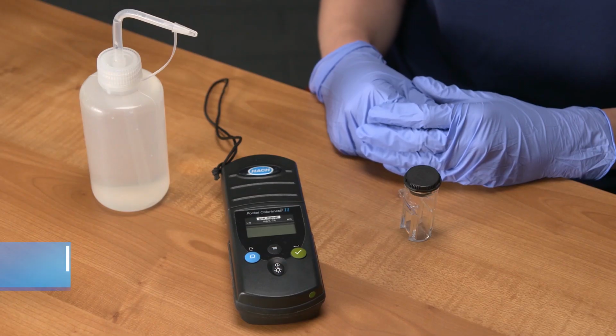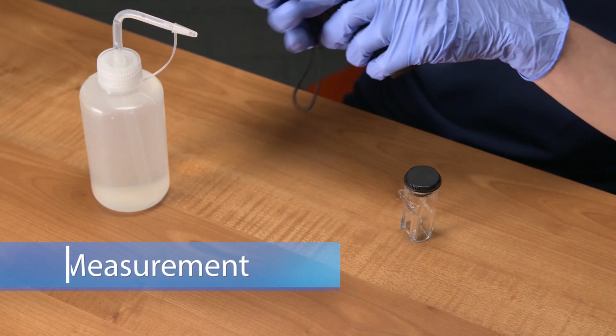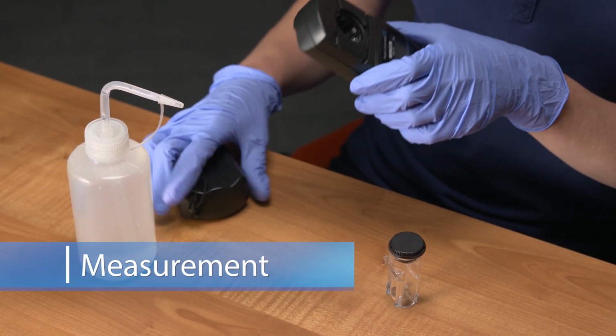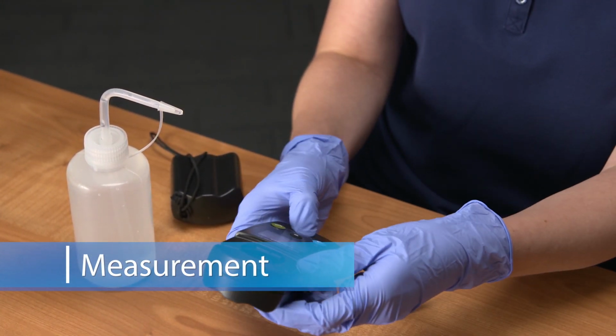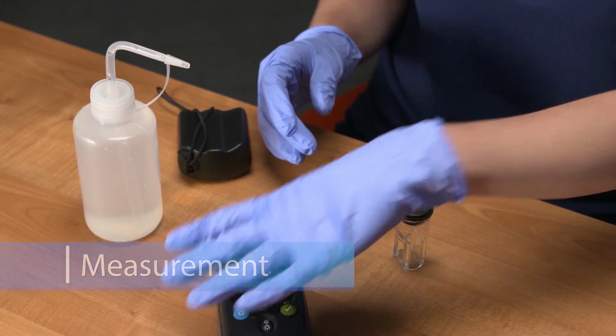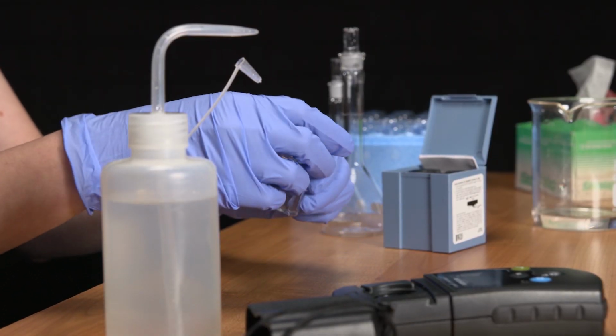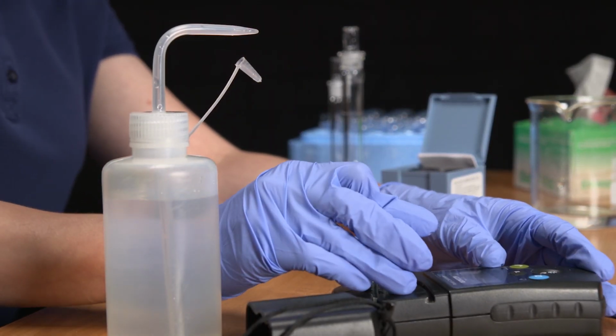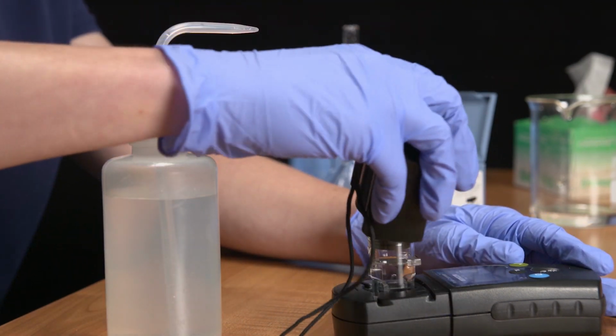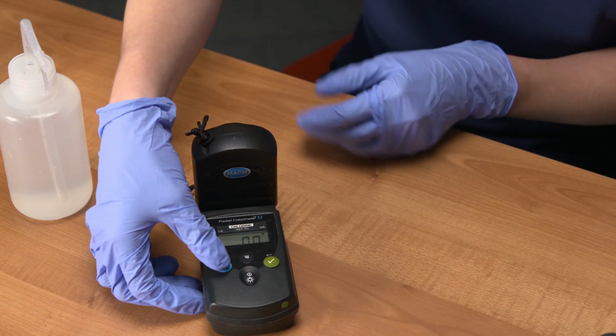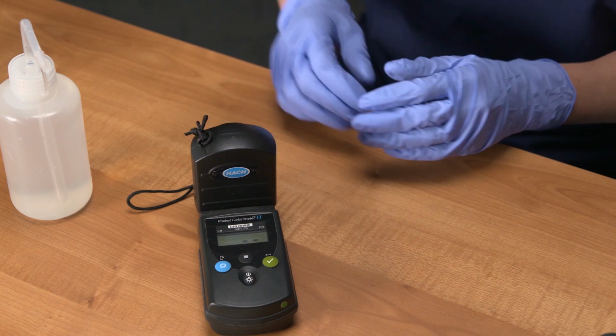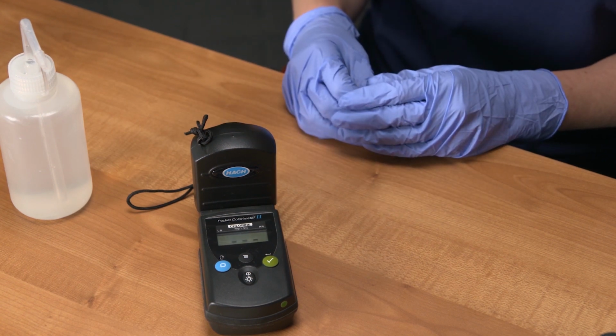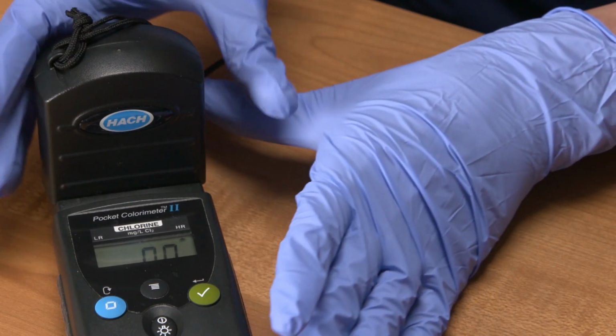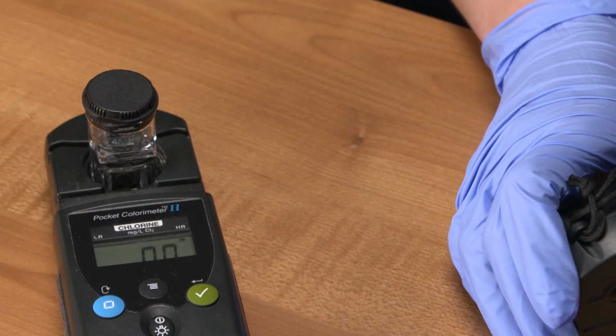Now we'll perform our measurement. First, we turn on the colorimeter. Now we zero the instrument. Be sure to rinse the vial with reagent water and a small amount of standard, then wipe clean. Ensure that the vial is aligned properly and according to manufacturer's recommendations. Now we remove the vial and add our DPD reagent.